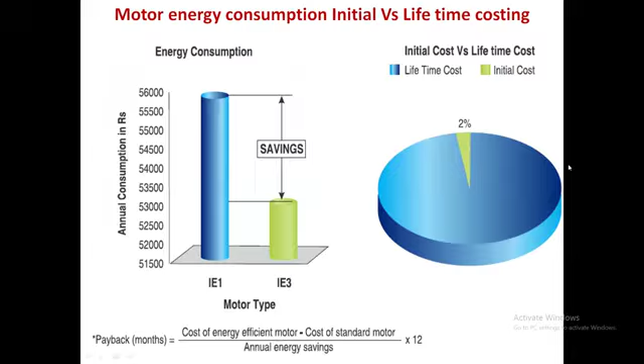You can see, from initial cost to running cost, almost 99% of the running cost goes towards the power. So always pick the best, most efficient motor that is possible. The IE5 motors, again, the induction motors are what we have studied, and then the permanent magnet synchronous motor. This is a change, like from CFL to LED is a big change. A CFL or a GLS bulb gave more heat, whereas an LED gives more light.